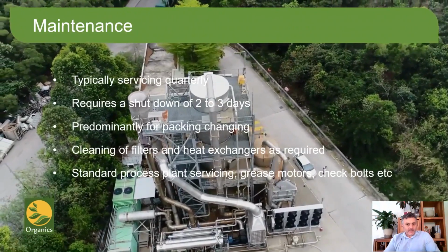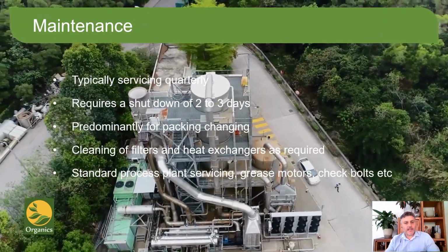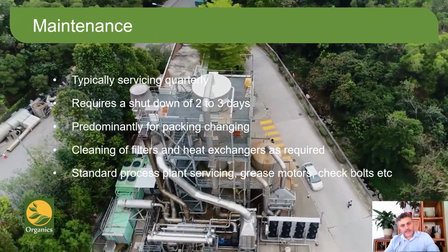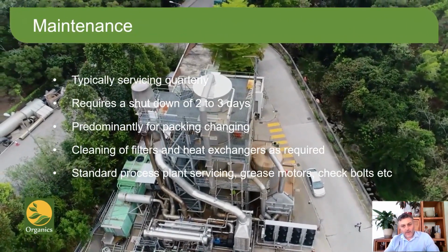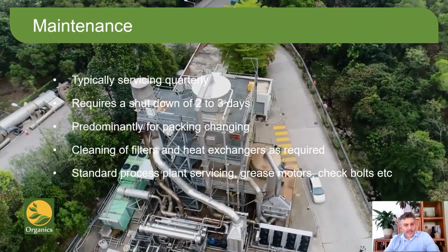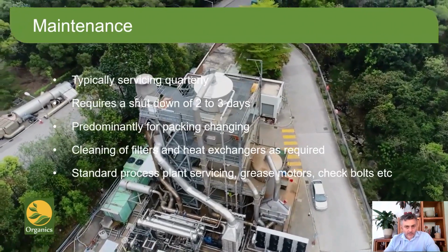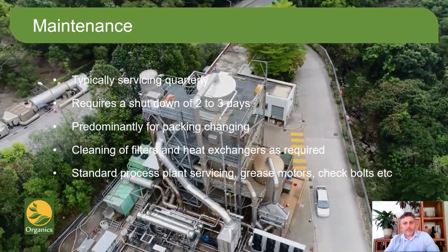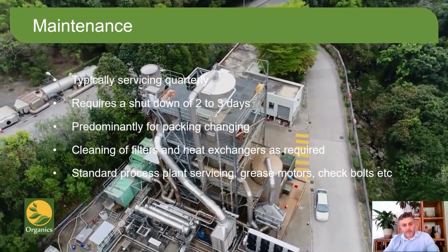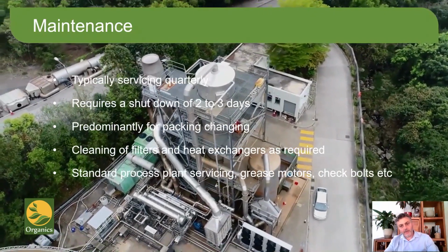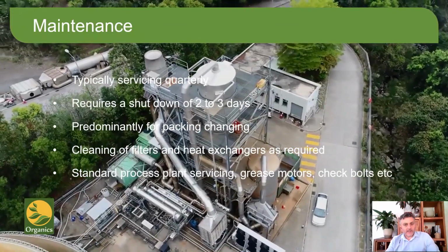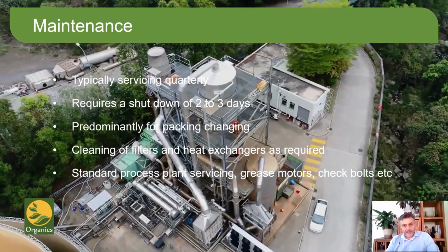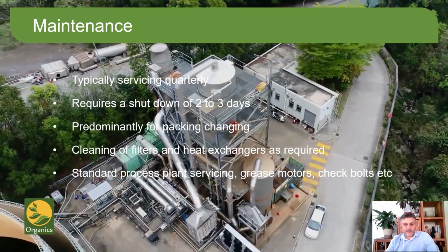Once the service interval has been established, what does it entail? Typically, the service is required every 3 or 4 months and will take around 2 to 3 days. The bulk of the work is in removing the dirty packing and replacing it with clean packing. Most sites hold a complete set of packing on site that they clean at convenient times while the plant is running, so that it is ready for use at the next service.